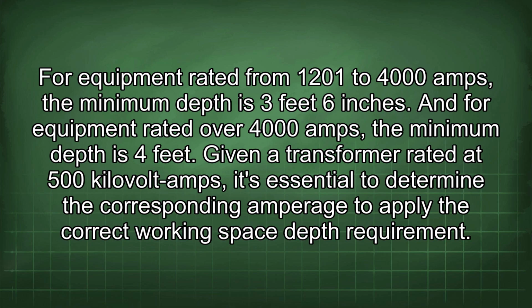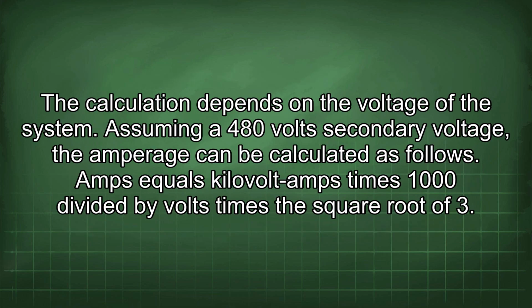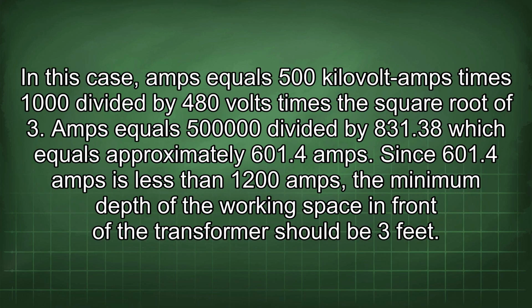Given a transformer rated at 500 kVA, it's essential to determine the corresponding amperage to apply the correct working space depth requirement. The calculation depends on the voltage of the system. Assuming a 480 volt secondary voltage, the amperage can be calculated as follows. Amps equals kilovolt-amps times 1000 divided by volts times the square root of 3. In this case, amps equals 500 kVA times 1000 divided by 480 volts times the square root of 3.